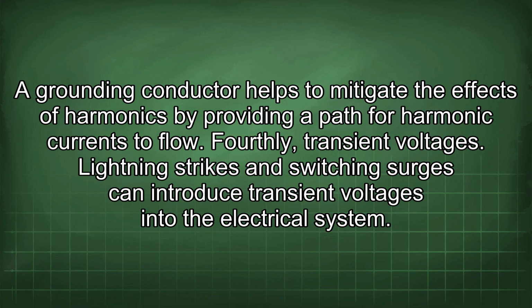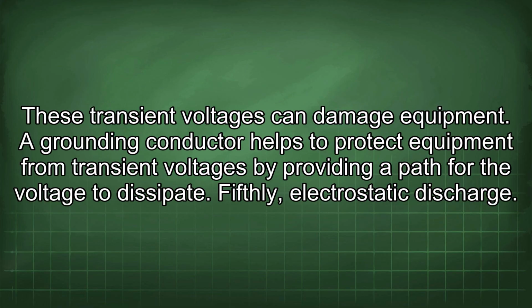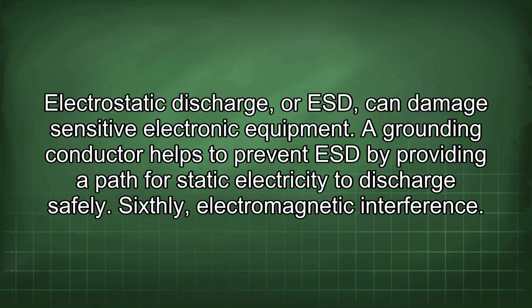Fourthly, transient voltages. Lightning strikes and switching surges can introduce transient voltages into the electrical system. These transient voltages can damage equipment. A grounding conductor helps to protect equipment from transient voltages by providing a path for the voltage to dissipate. Fifthly, electrostatic discharge. Electrostatic discharge, or ESD, can damage sensitive electronic equipment. A grounding conductor helps to prevent ESD by providing a path for static electricity to discharge safely.